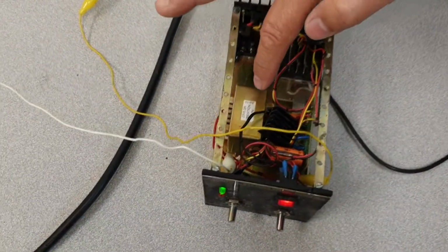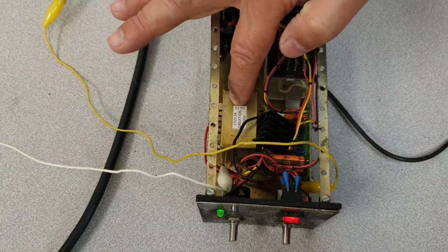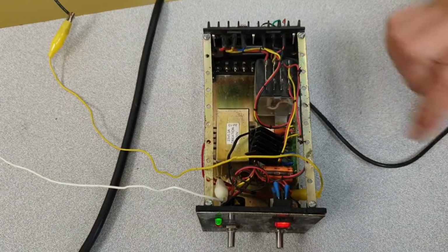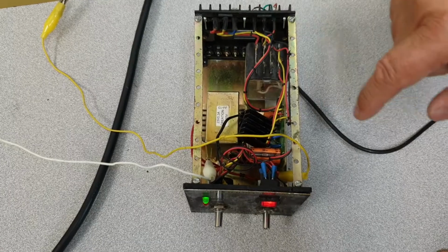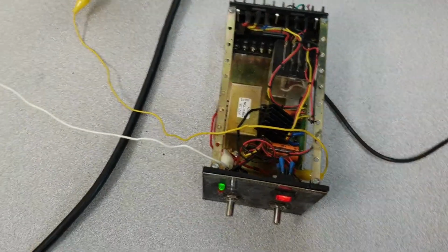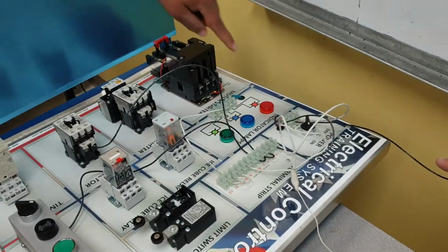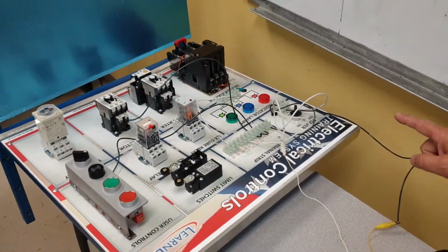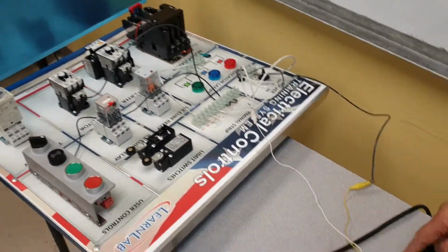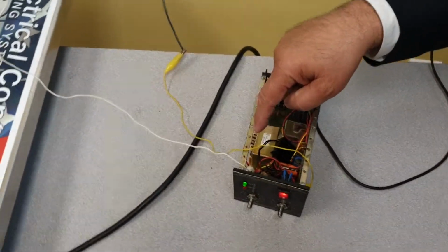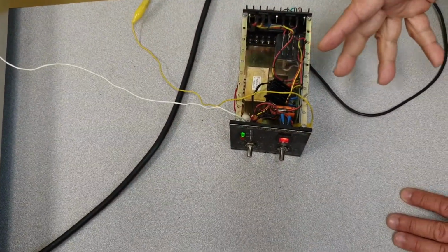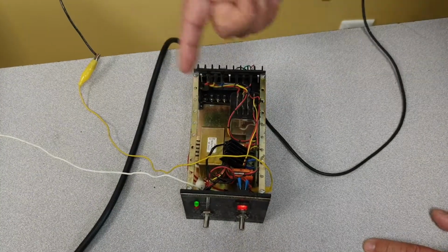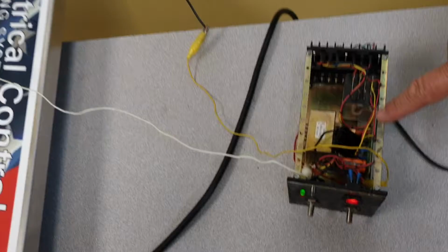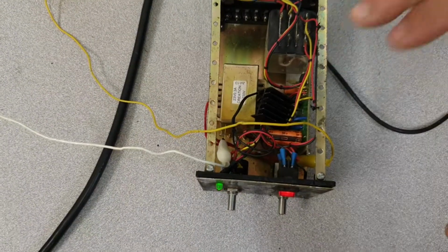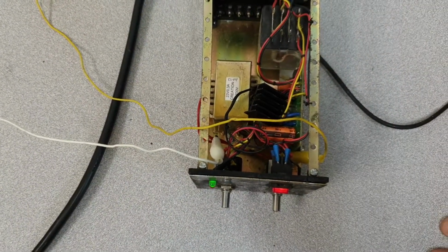I noticed this transformer's primary is 230 volts, but the secondary is 23 volts AC, which feeds the circuit. I realized we have a board with an output of 24 volts, so we could feed that AC into the secondary of the transformer and check everything. We connected the 24 volts to the secondary of the transformer, and in the primary we had 230 volts. So we know for a fact that the transformer works.